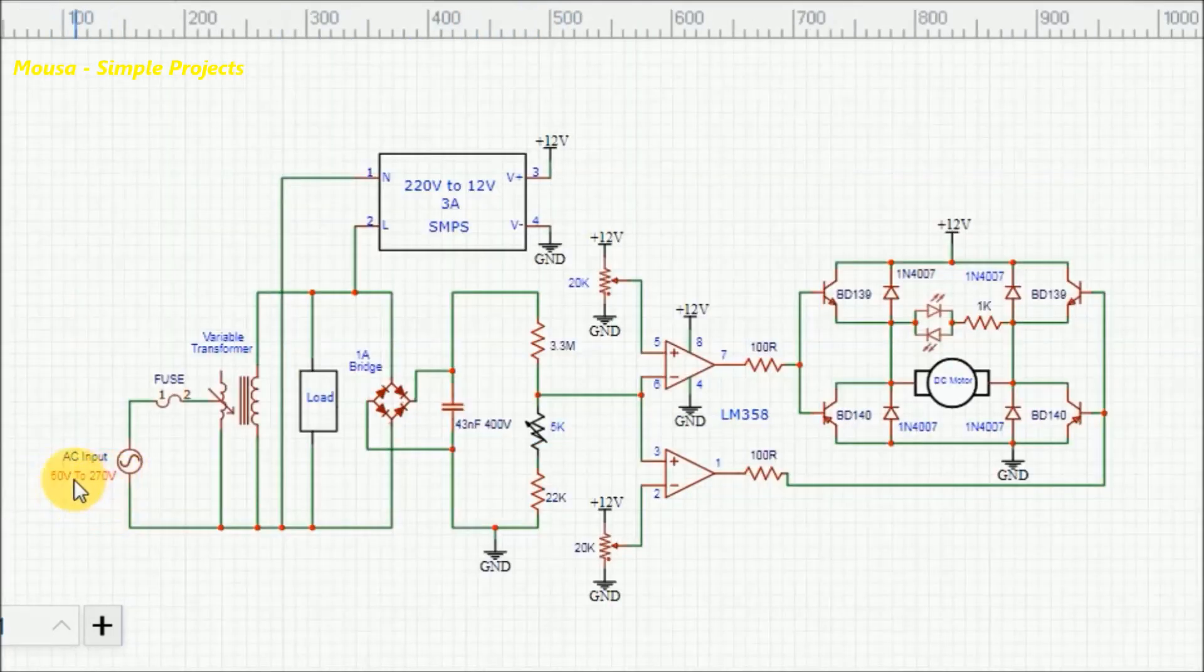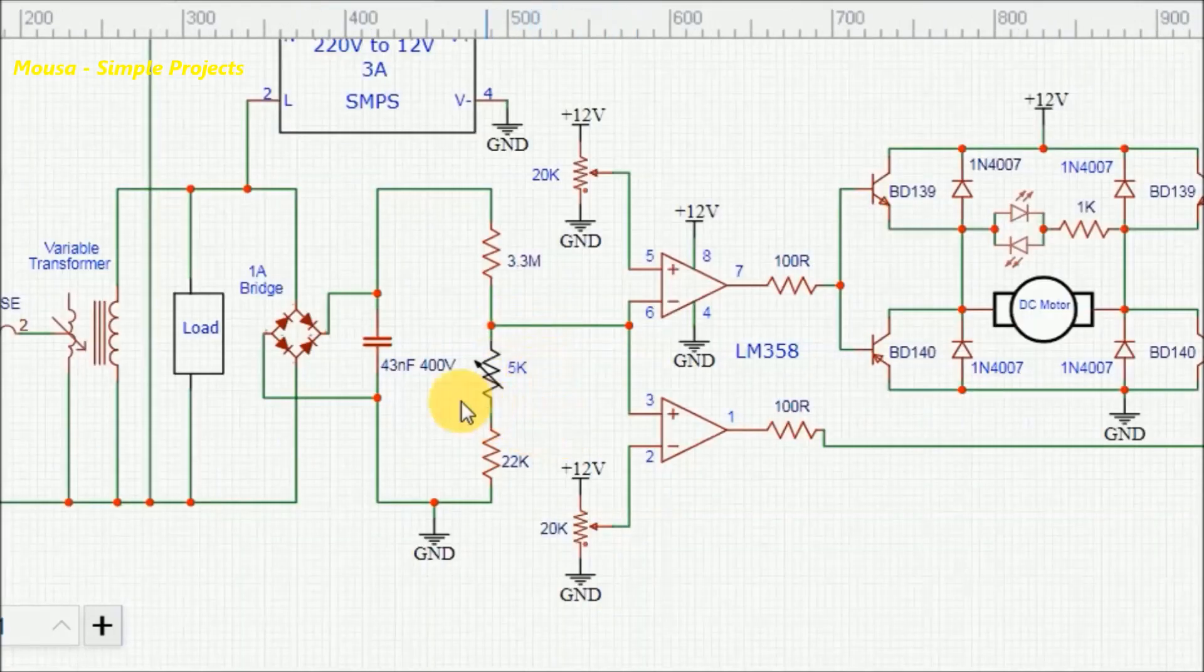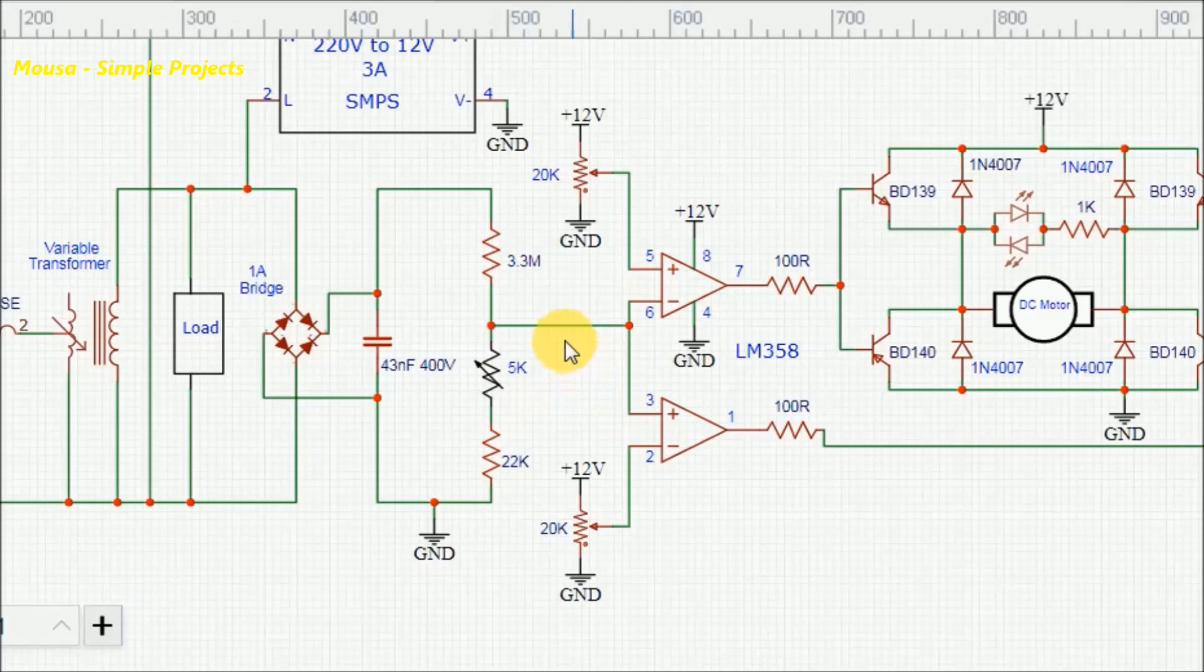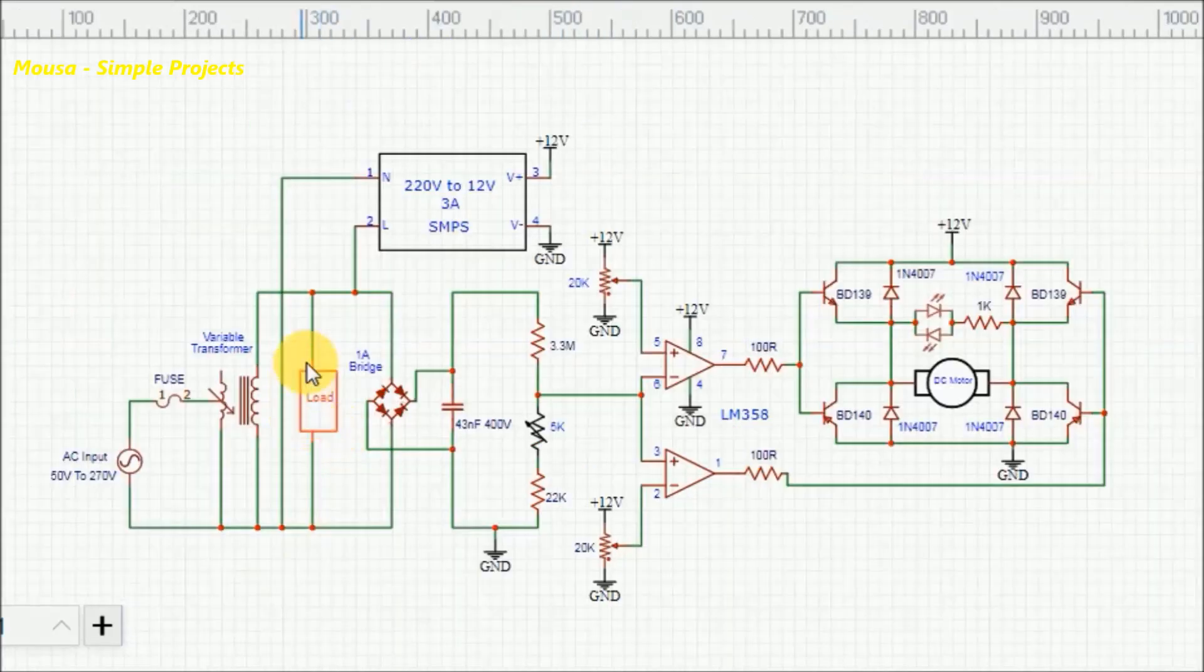The mains voltage with unstable value is connected to the primary of the transformer. The secondary side of the transformer is connected to the load. Here we have three potentiometers. You have to preset them at the beginning. The voltage at this point should be equal to the voltage of the secondary side of the transformer divided by 100.